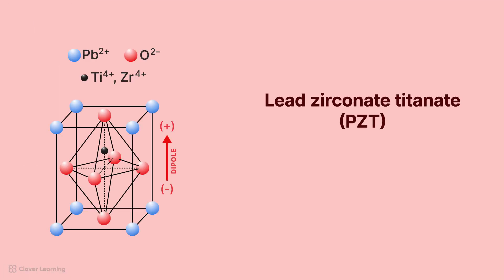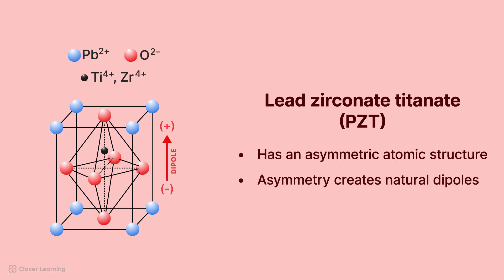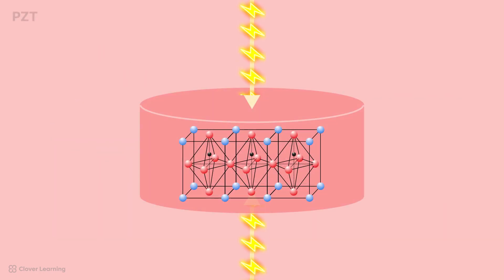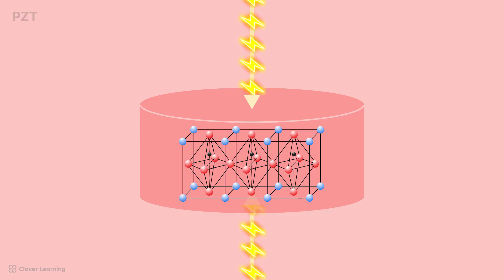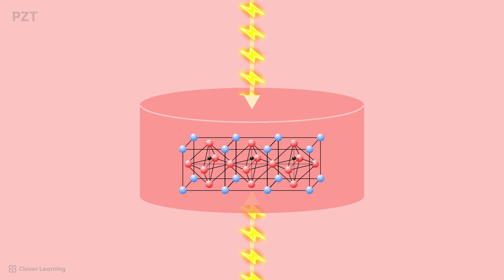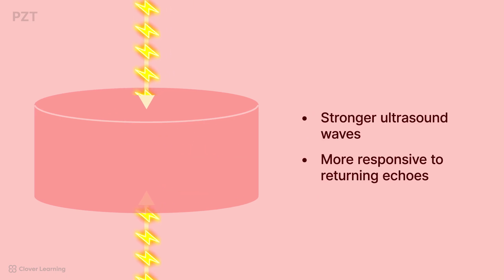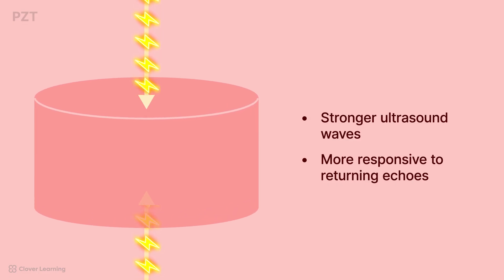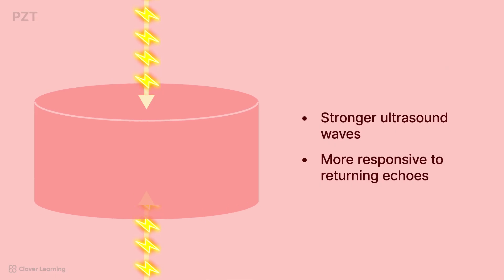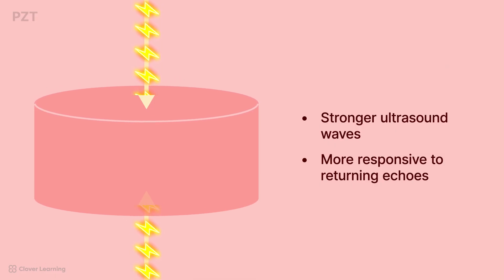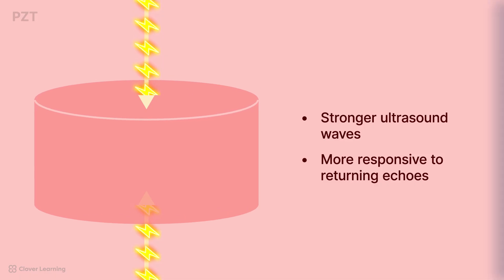This is because PZT has an asymmetric atomic structure. This asymmetry creates natural dipoles, or regions of positive and negative charge, within the material. When an alternating electrical current, or AC, is applied to the crystal, the electric field interacts with the dipoles, causing them to align or shift within the crystal lattice and distort or deform the crystal. The alternating current stimulates the crystal to repeatedly expand and contract in response to the changing electric field. This quality of the piezoelectric effect creates stronger ultrasound waves and makes it more responsive to the returning echoes.